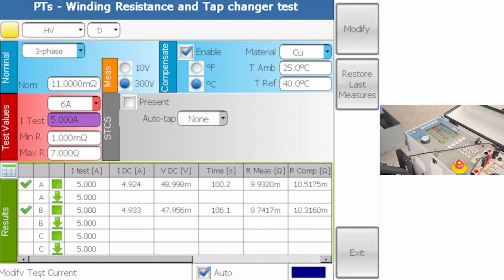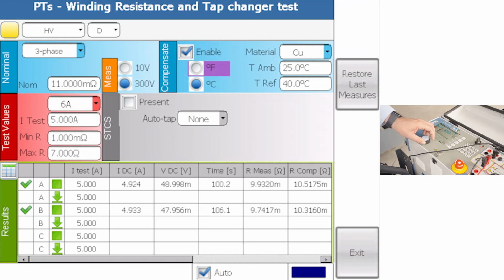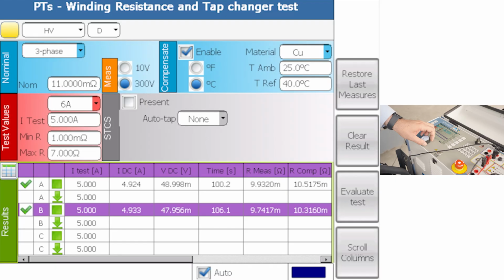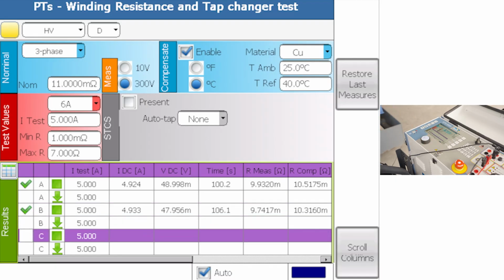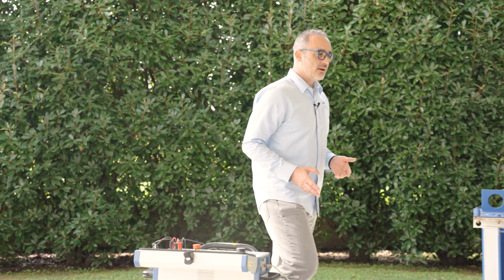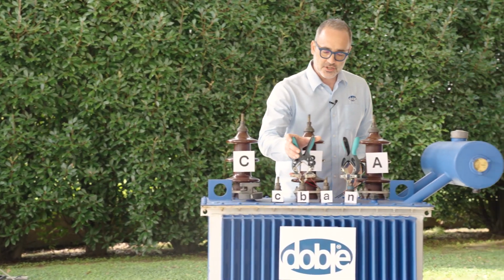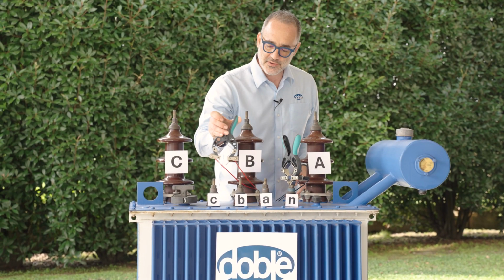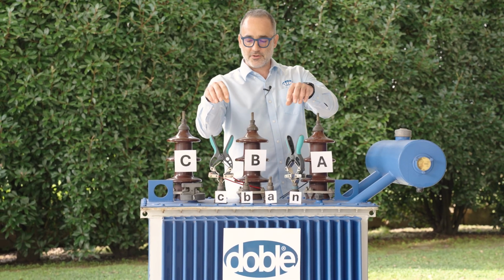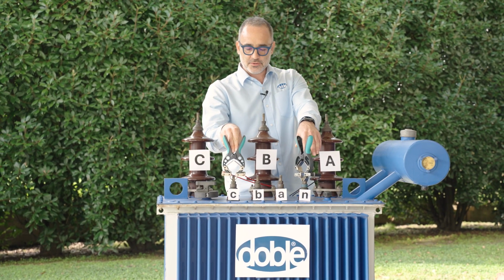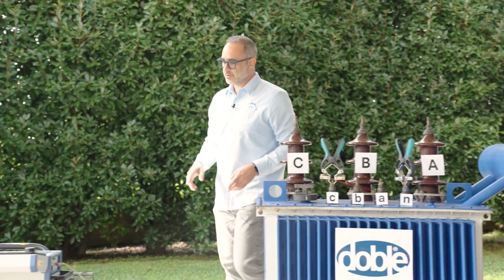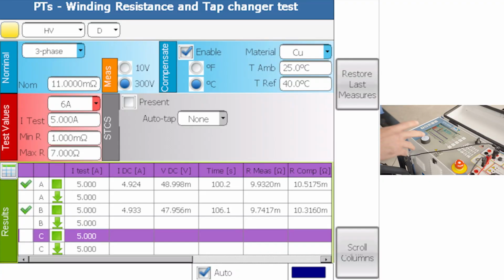All right, STS measured the resistance of phase B, and we can compare 9.9, 9.7. This is very close, but let's also measure phase C so that we can be sure. Let me move to the transformer and change the connections to C. How do we do that? Once again, we just change the generation from phase B to phase C. So now we will generate current between phase C and the neutral, and measure the voltage drop. Now let me do that, and now I press start.